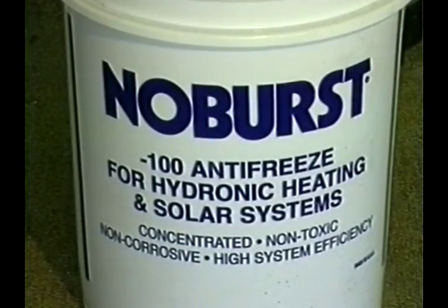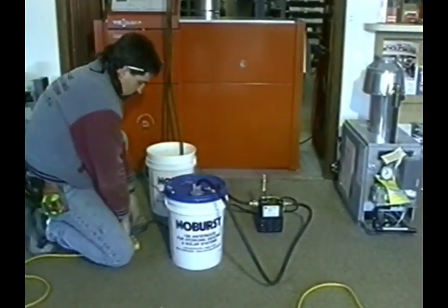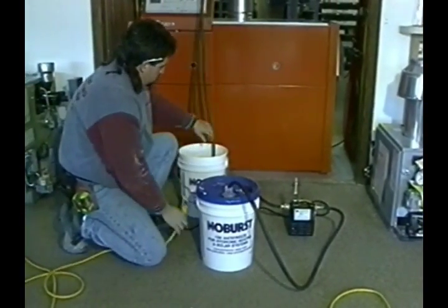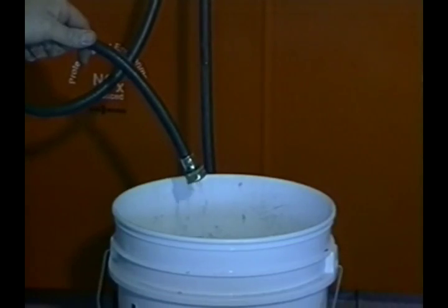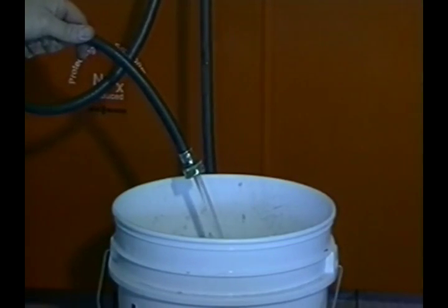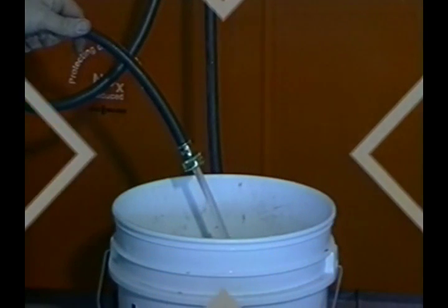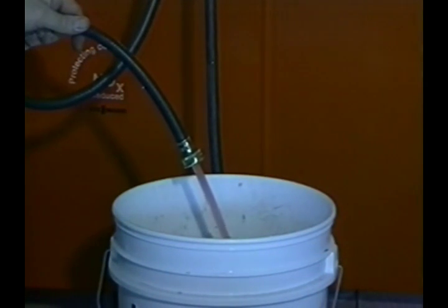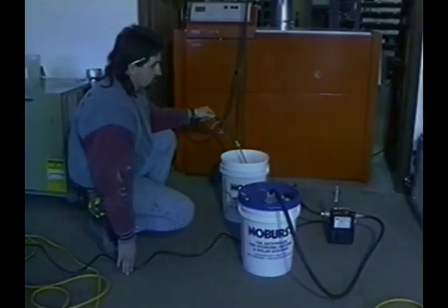System treatments are not necessary, but recommended as they prolong the life of system components. There are several types of system treatments available. Some are silicate-based, non-chromate treatments. If freeze protection is desired, non-toxic propylene glycol can be added. The amount of glycol used in the system is based on the degree of freeze protection desired. In no case should automotive antifreeze be used in a heating system. Automotive antifreeze can damage system components and it is toxic.